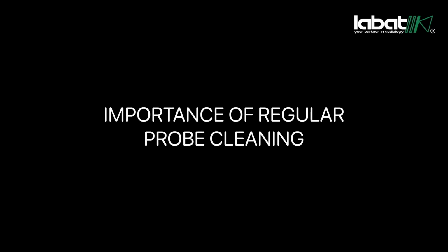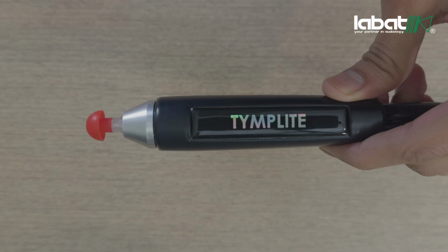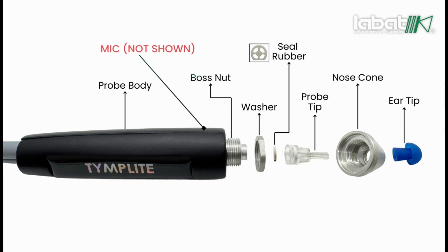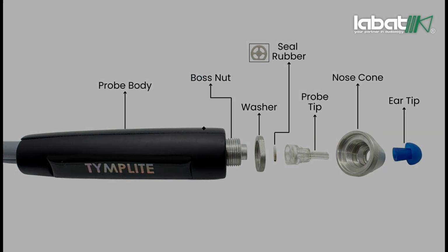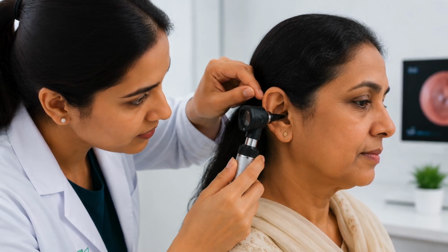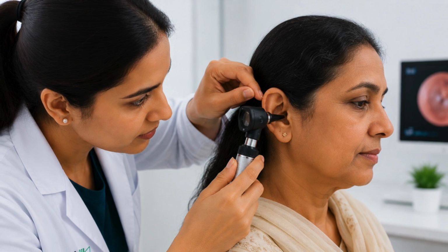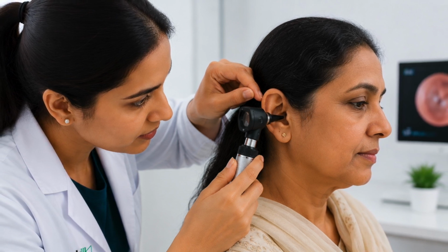Importance of regular probe cleaning. Regular cleaning of the probe is essential. If cleaning is not performed routinely, earwax may enter the interior of the probe and damage the microphone and speakers, thereby rendering the probe inoperational. To minimize the risk of wax deposition, it is strongly recommended to perform an otoscopic examination of the patient's ears prior to administering the tympanometry test.